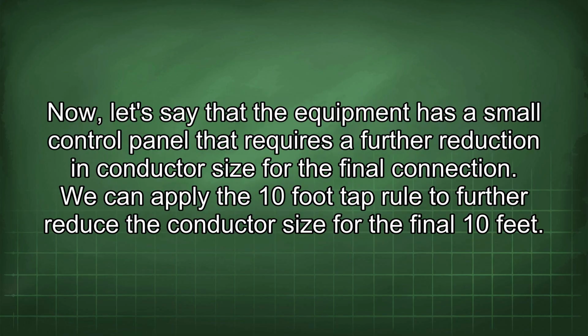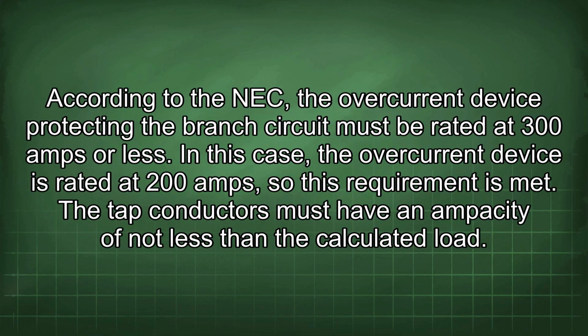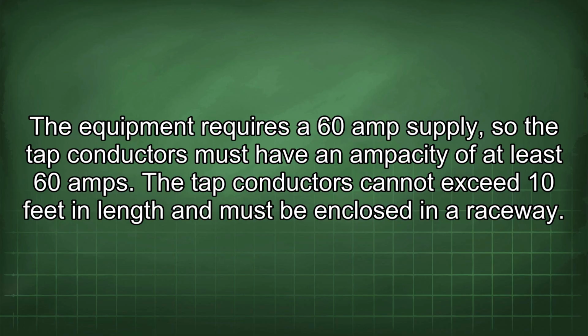Now, let's say that the equipment has a small control panel that requires a further reduction in conductor size for the final connection. We can apply the 10-foot tap rule to further reduce the conductor size for the final 10 feet. According to the NEC, the overcurrent device protecting the branch circuit must be rated at 300 amps or less. In this case, the overcurrent device is rated at 200 amps, so this requirement is met. The tap conductors must have an ampacity of not less than the calculated load. The equipment requires a 60 amp supply, so the tap conductors must have an ampacity of at least 60 amps.